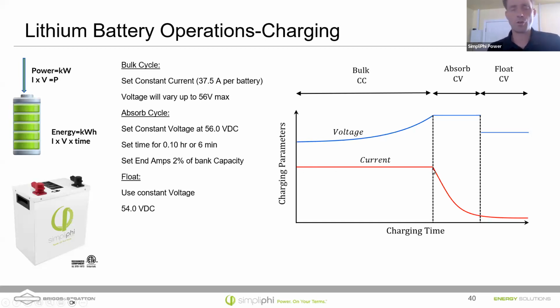Now, as long as your charging equipment can maintain that current, so if you're running off of solar and it's not able to produce that full current, it will charge as fast as it can up to that limit at a constant current. But notice, as we start to charge a battery up, what happens is the voltage that we have to apply to charge that battery starts to rise, right? So if I'm putting 37.5 amps in a fully discharged battery, I don't have to apply a very high voltage to get that. I might be able to do that at 52 volts.